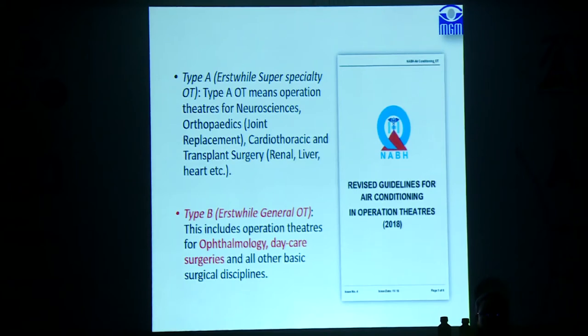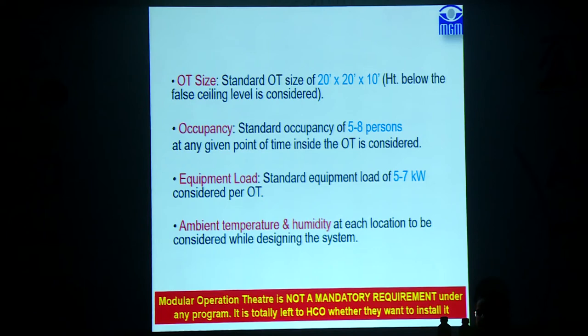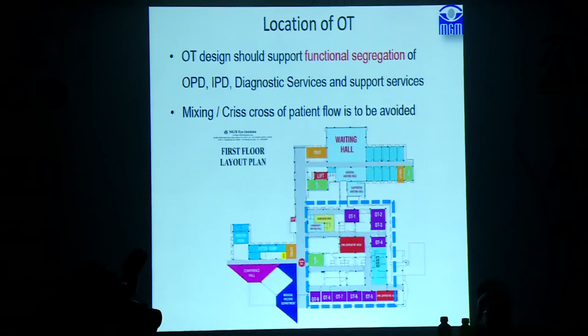There are revised guidelines from NABH, mostly applicable when installing air conditioning systems, edited in 2018 as the latest version. They give standards such as OT size should be around 20x20 feet, with specified height. Standard occupancy in the theater at any point of time should be 5 to 8 persons, with an equipment load of 5 to 7 kilowatt per OT. Ambient temperature and humidity at each location are to be considered. Modular theaters have become popular with many vendors, but they are not a mandatory requirement and involve significant cost, so a standard OT is also acceptable.